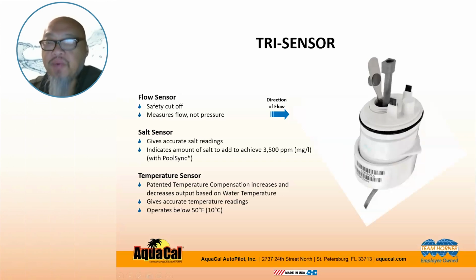There's a couple of things that we do with the temperature sensor that make this more unique. We've got this feature called the automatic temperature compensation feature. Again, no one else offers this feature. What that tells me is that when the water temperature increases, there's typically a higher chlorine demand, so we need more chlorine. As a result, our unit will increase output to generate more chlorine as water temperature increases. On the other side, when water temperature decreases, it will reduce the output.